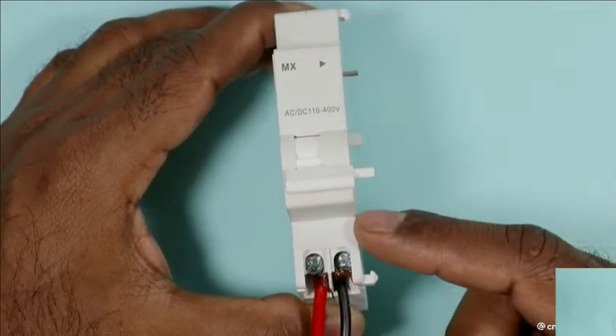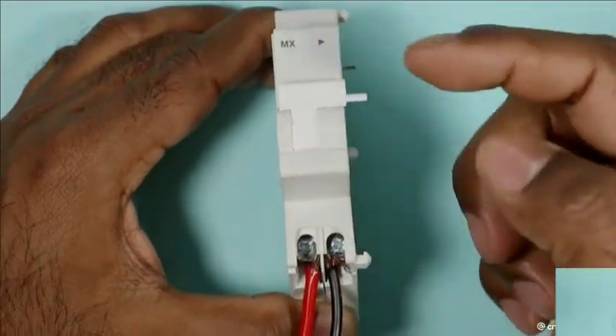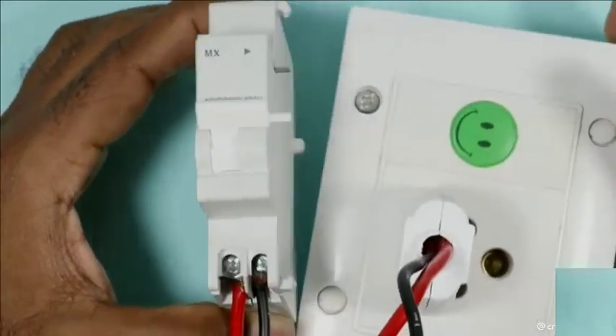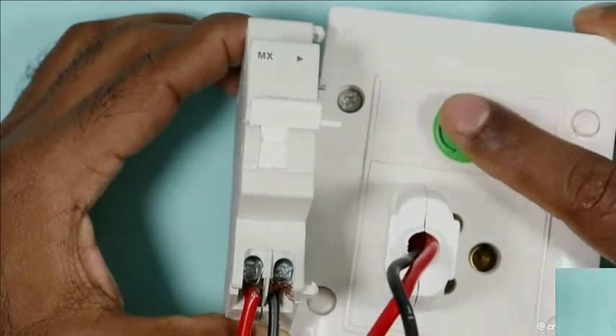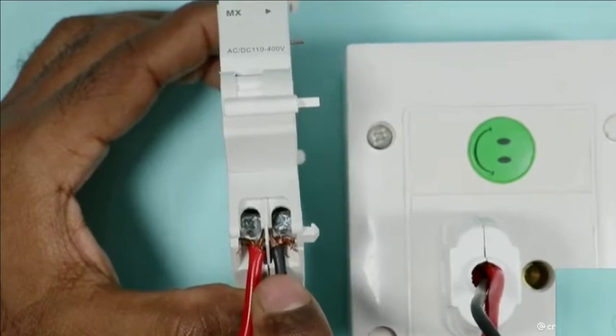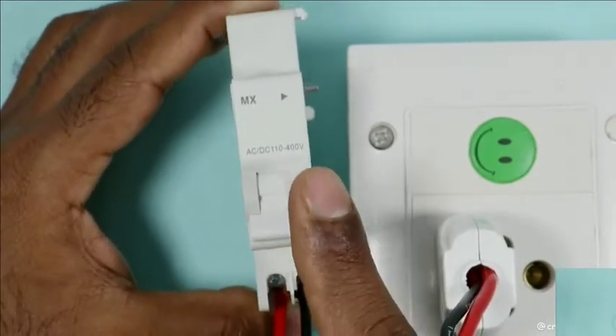Let's see one more time. I turn this on and after this I am going to turn on the power supply through this socket. When I press this, shunt release coil will trip. This means if we provide power supply to these terminals, then this shunt release coil will trip.